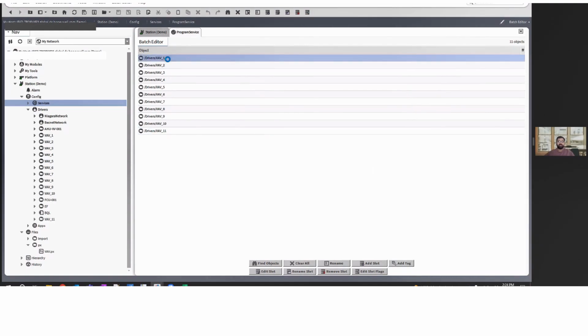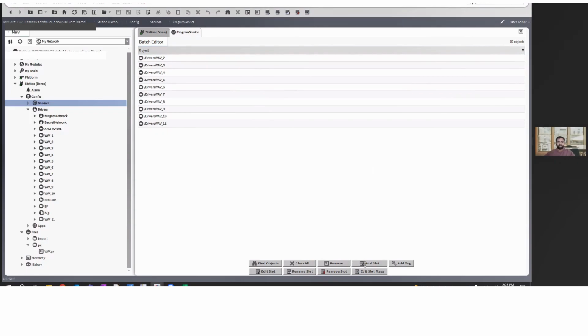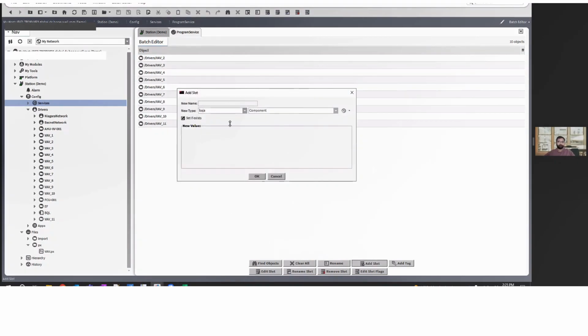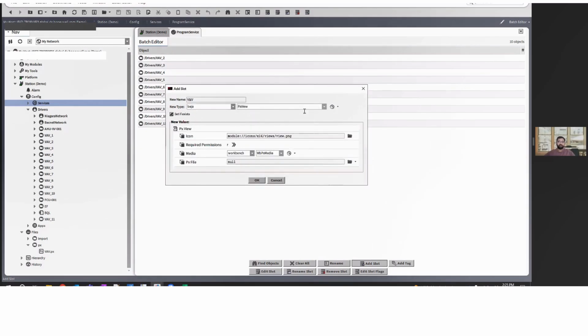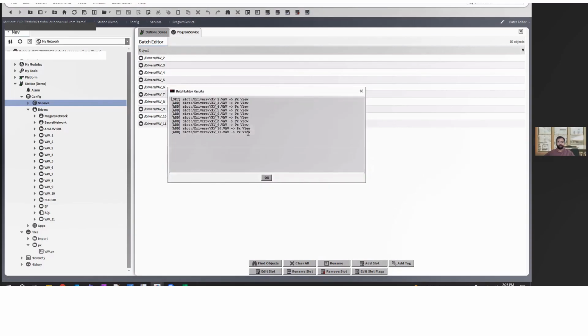Since I have already assigned the VAV to VAV1, I will delete it from this view and go to add slot. I'll type in the name VAV and the PX view. Once I do that, you'll see the PX view come up here, change the view and define the PX file, and hit OK. Once I do that, the VAVs have been assigned the PX.